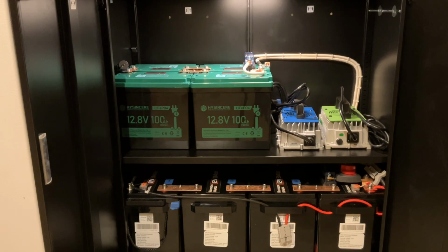You're basically limited to about 5,000 watts of consistent load on that inverter, which is capable of substantially more, and surging to more than twice the inverter's output would definitely overload those BMS and either damage them or cause them to shut down. So the second set of batteries was ordered because they were such a good deal in December, to add surge load capability, as they have an internal 100 amp BMS as well.